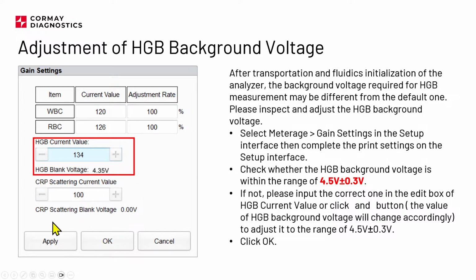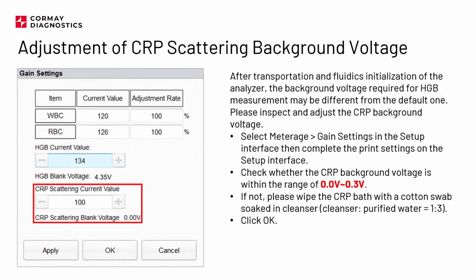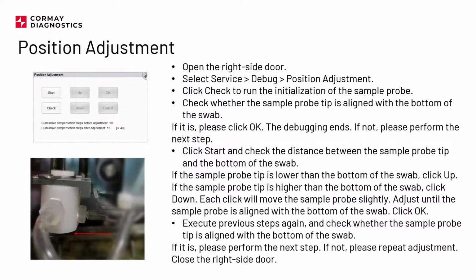And the same thing is for CRP scattering blank voltage. In most of the cases, you will not need to make any adjustments here in this menu. But from my experience, I had one analyzer where I needed to make this adjustment because the voltage was too small, basically. So it was out of range, and the analyzer just gave an error in that case. So here is also information for the CRP scattering blank voltage. So the range is also specified here.